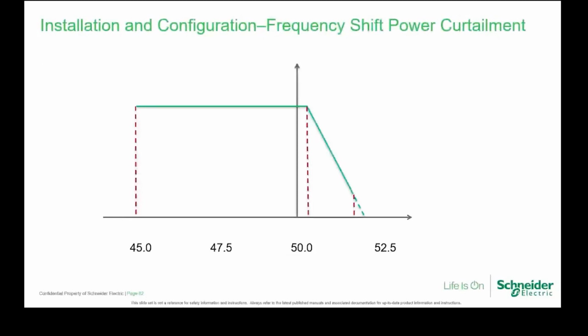Because it's first a frequency start and a frequency stop and disconnect, and then we have the ramp rate. Now the ramp rate, from my experience, I had to change it several times so that the inverter doesn't cycle off too often. There's a bit of leeway, a bit of hysteresis built in, but it will take a bit of trial and error to get the optimal ramp rate. We give a recommended ramp rate for the RL, but in real life sometimes it needs to be tweaked a bit to make sure it doesn't do too many cycles. And that's the RL power output. As you can see, it varies from the frequency start to the frequency stop and then disconnects if it gets too high.